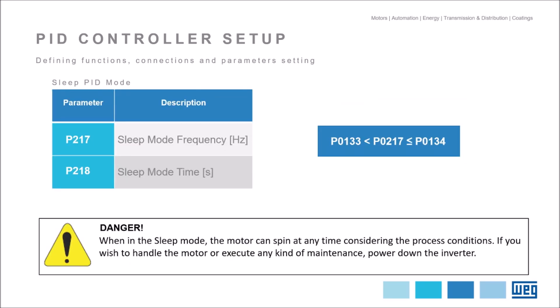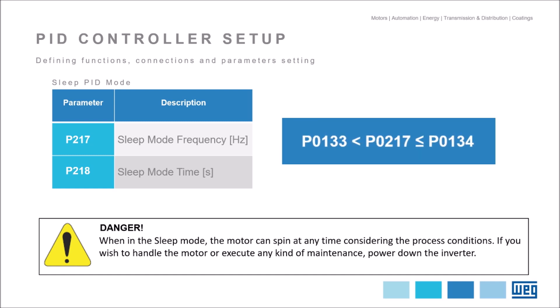In some applications such as pumps, the inverter has a feature that can reduce power consumption even more. It is called the sleep function, which shuts down the motor at low speeds when there is no need for the motor to maintain the process variable stable. This function is enabled by setting P217 (sleeping frequency) and P218 (sleeping time). When the motor operates at a frequency below the value set in P217 for longer than the time defined in P218, the motor will stop. On a pump, when the pressure drops below the set point value, the motor will restart. Note that P217 must be adjusted within the maximum and minimum frequency limits.